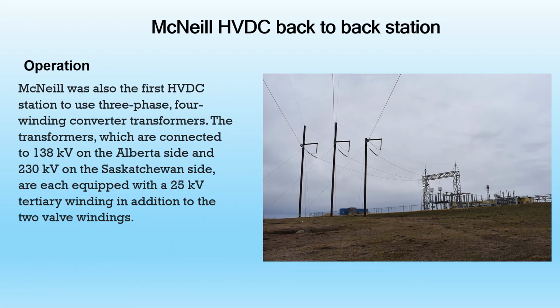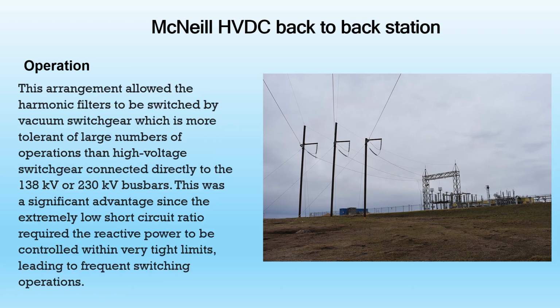McNeill was also the first HVDC station to use three-phase 4-winding converter transformers. The transformers, which are connected to 138 kV on the Alberta side and 230 kV on the Saskatchewan side, are each equipped with a 25 kV tertiary winding, in addition to the 2-valve winding. This arrangement allows the harmonic filters to be switched by vacuum switchgear, which is more tolerant of a large number of operations than high voltage switchgear connected directly to the 138 kV or 230 kV busbar. This was a significant advantage, since the extremely low short circuit ratio required reactive power to be controlled within very tight limits, leading to frequent switching operations.